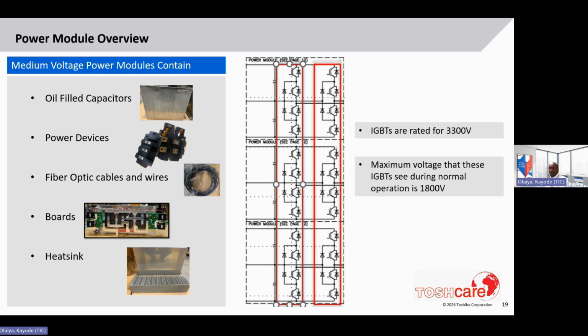Then finally here, showing the heatsink, which is what cools the power devices. This shown here is a heatsink for a frame 4 power module. So this is a bigger heatsink. Made a note there about the IGBTs. They're rated for 3300 volts, so they are actually medium voltage IGBTs, though the maximum voltage that they will see during normal operation is 1800 volts. So there is a lot of safety margin built into the IGBTs.